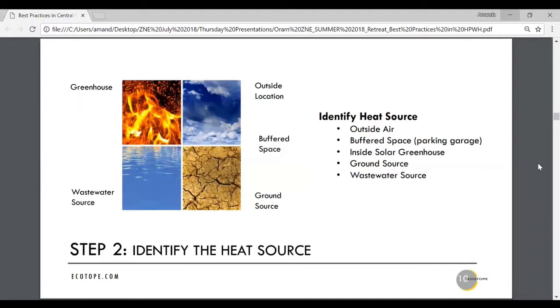Yes, we got it past the plumbing inspector. It was difficult. But you're not putting potable water through it—absolutely not. It's a totally separate double-wall heat exchange between the heat pump and the source. It's basically like a ground source heat pump, except minus the ground bores. We're just putting a heat exchanger inside a big bath of all the building's wastewater.